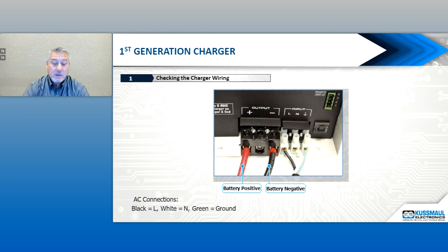It's very possible that one of these has come loose. If you have a problem with the charger, the first thing you want to do is double check the connections. Make sure they're secure. Look at your battery positive and battery negative, and also your line input, which is the alternating current coming into the charger. In North America, generally the black is the line, the white is the neutral, and the green is the ground. Double check to make sure those are correct, because if any of these are out of place, the charger won't operate properly.